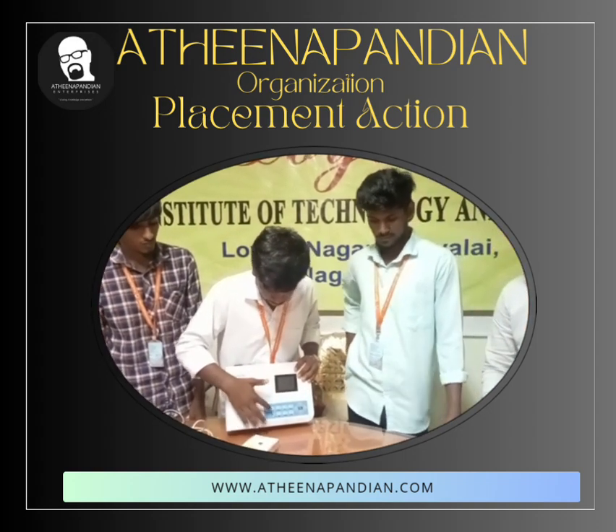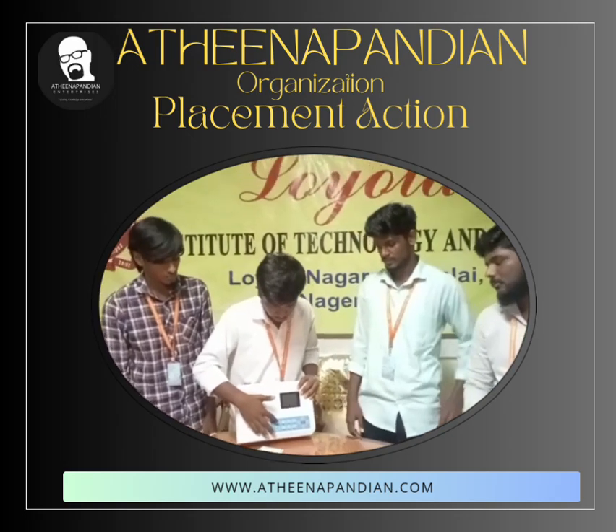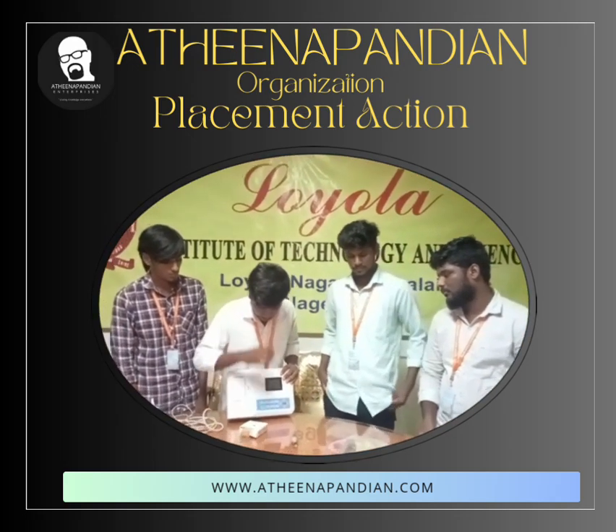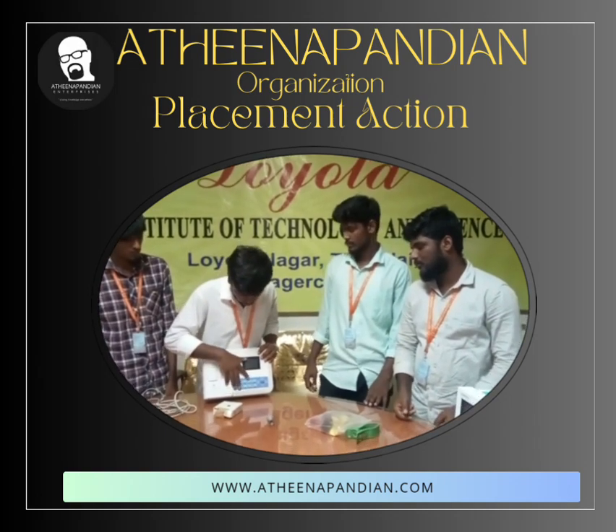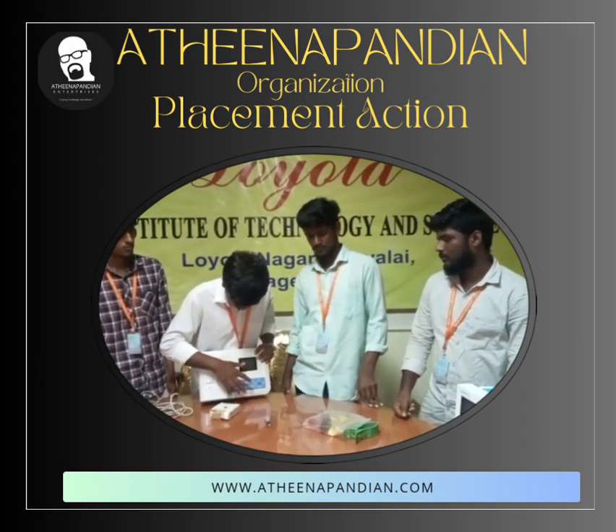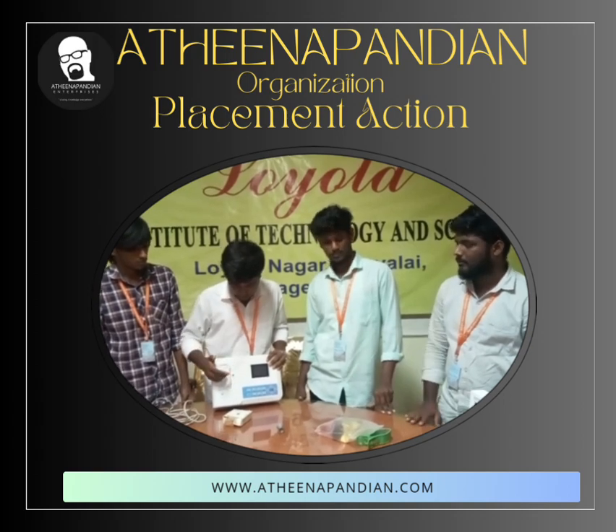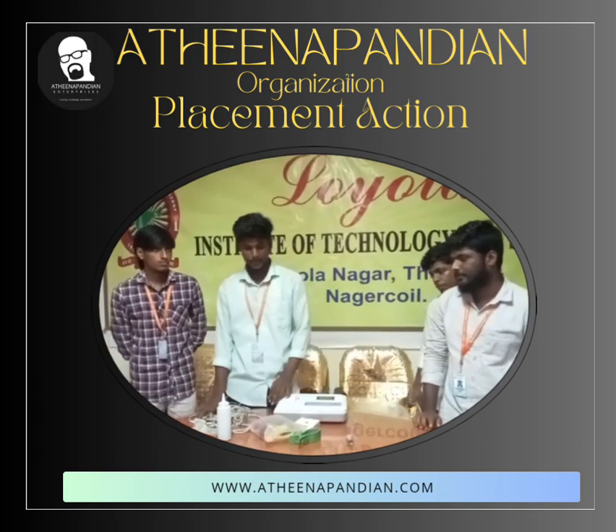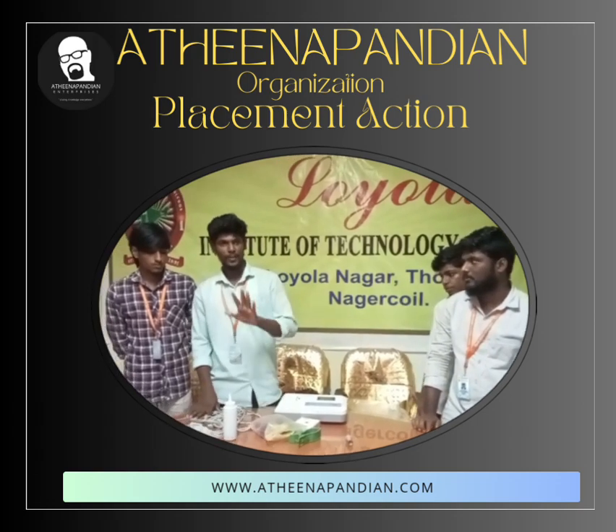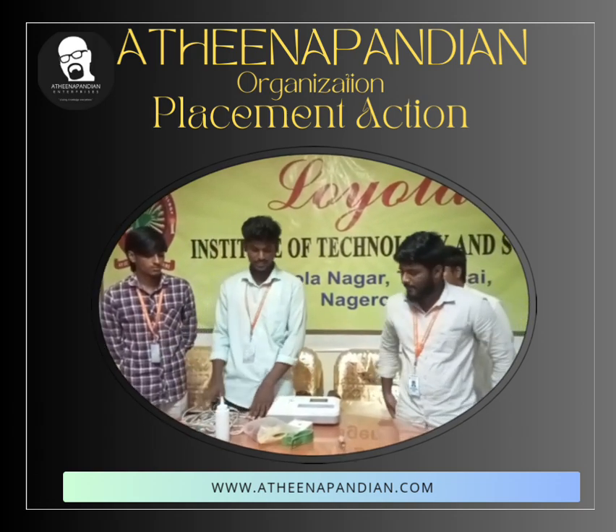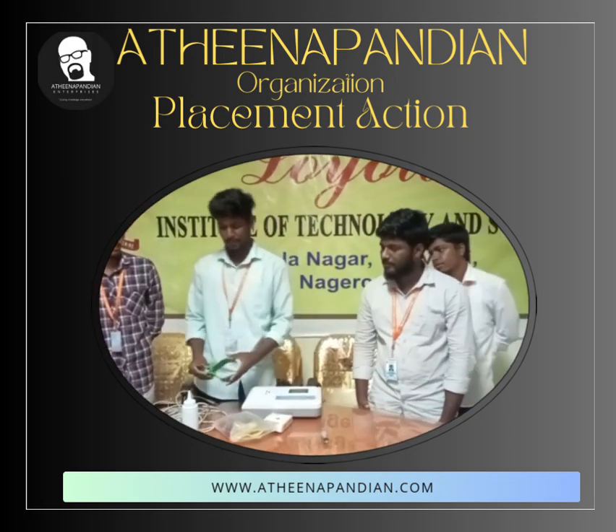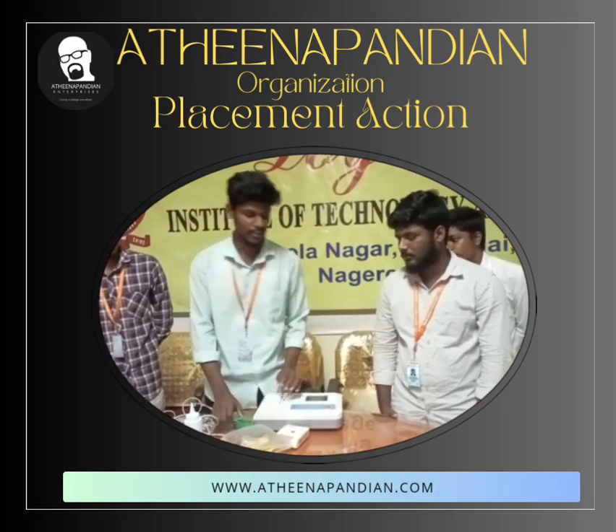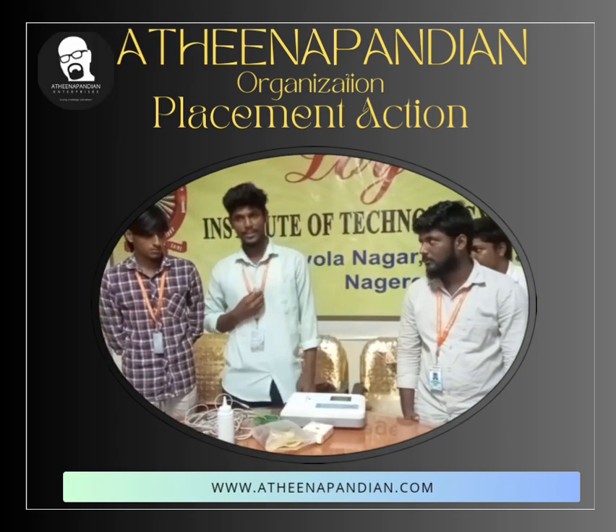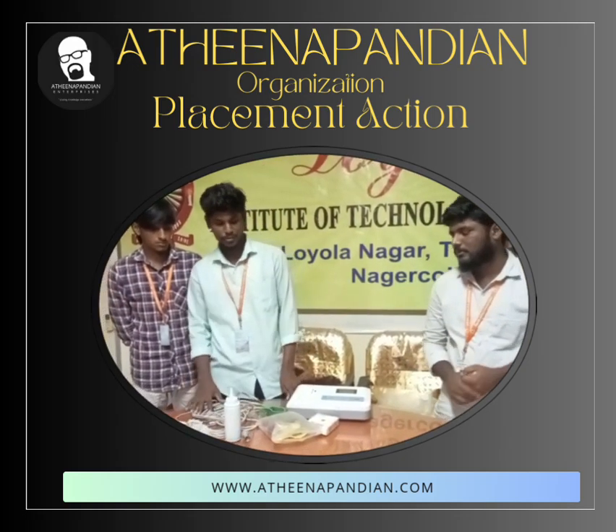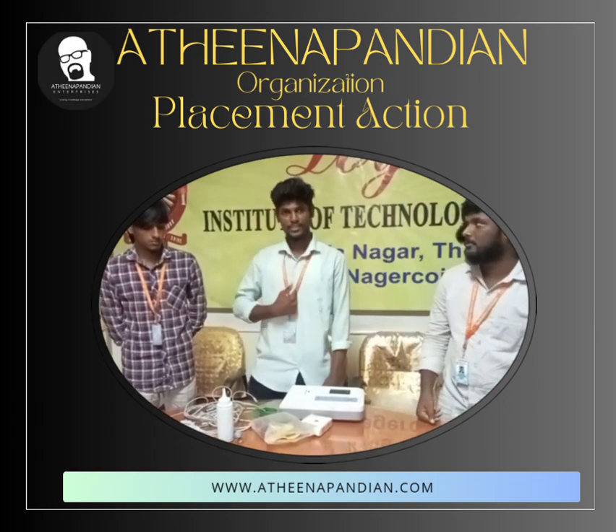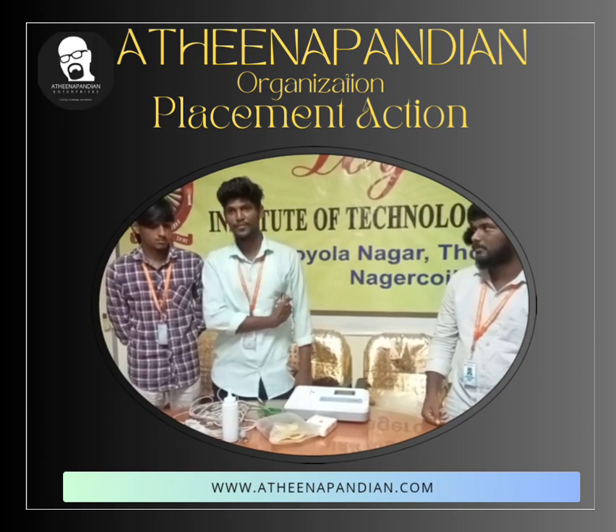The menu consists of brightness, contrast and other functions. The mode button changes the mode, and print is used to print the graph. The lead systems: the first is the 3-lead system, the second is the 5-lead system, the third is the 12-lead system. The 3-lead system uses only clamp electrodes. The 5-lead system uses an extra suction electrode fixed on the chest. The 12-lead system uses 6 suction electrodes V1, V2, V3, V4, V5, V6.